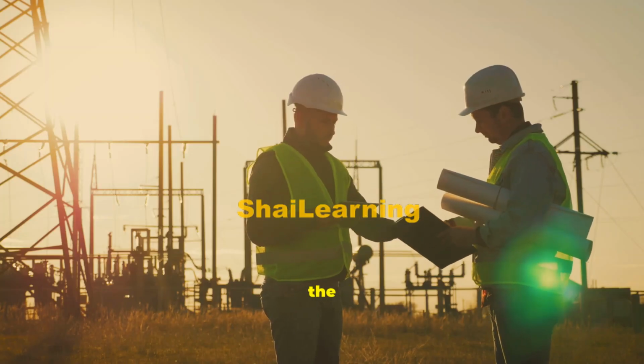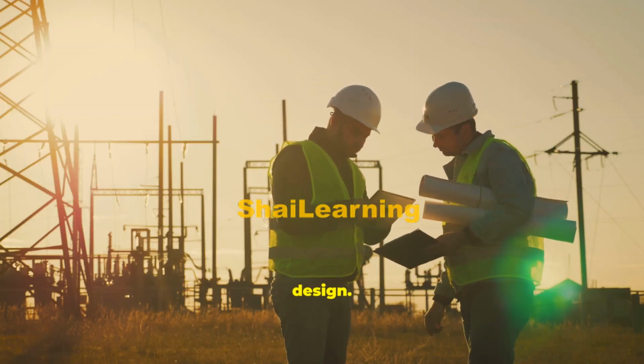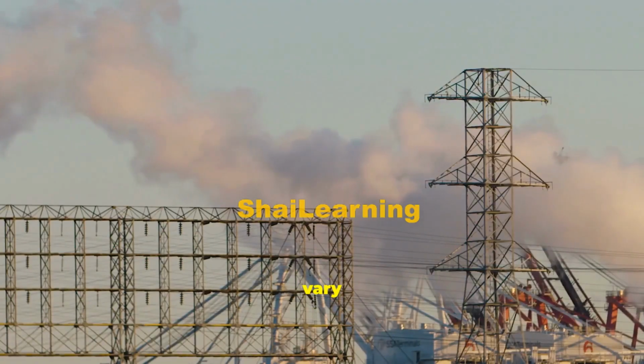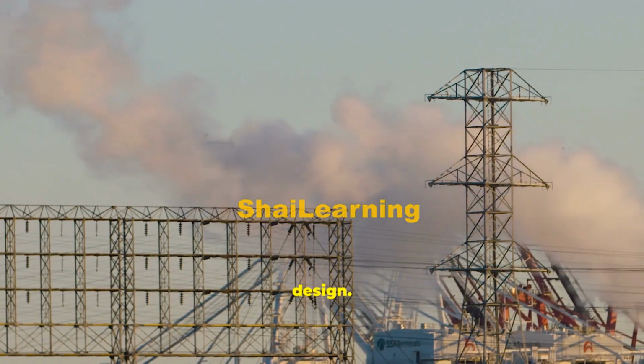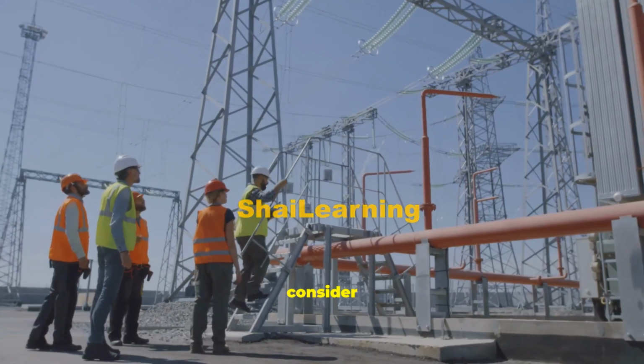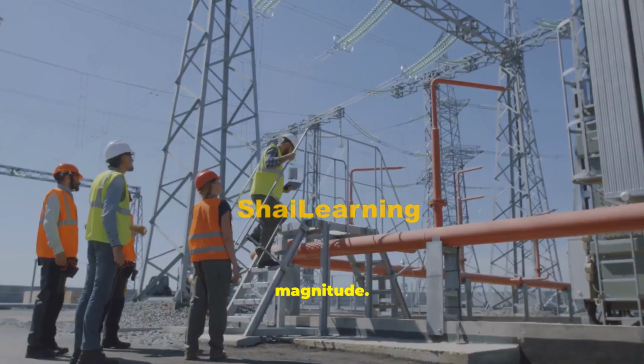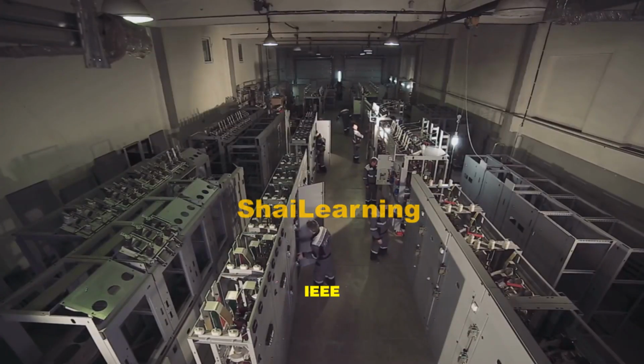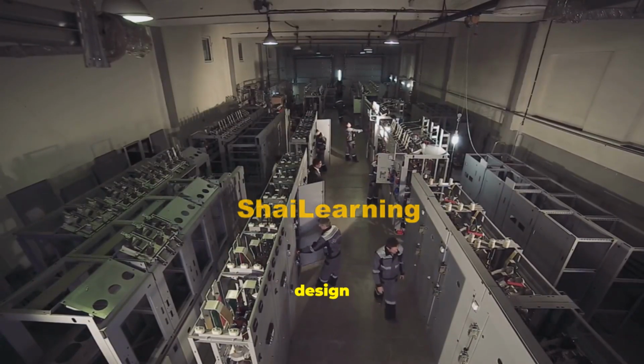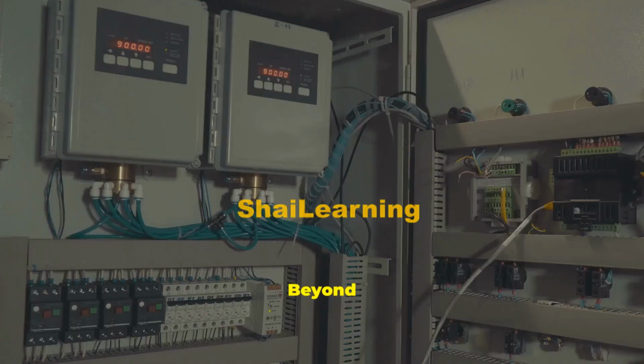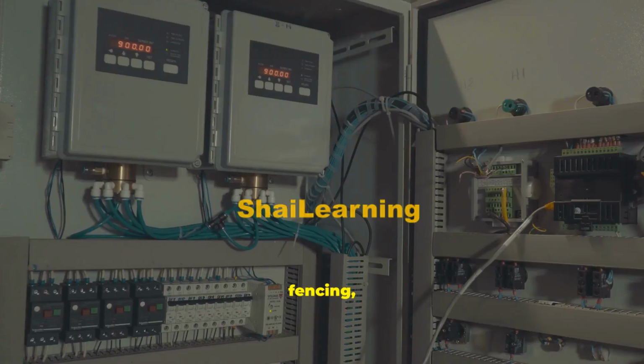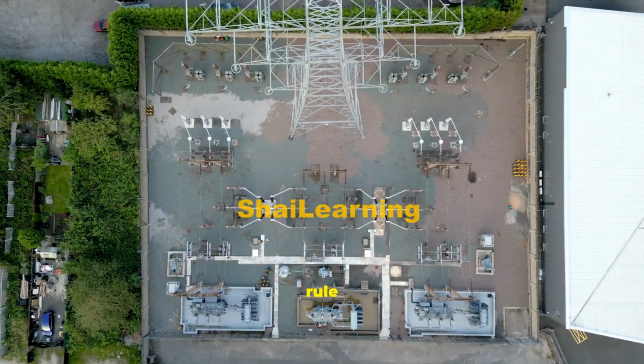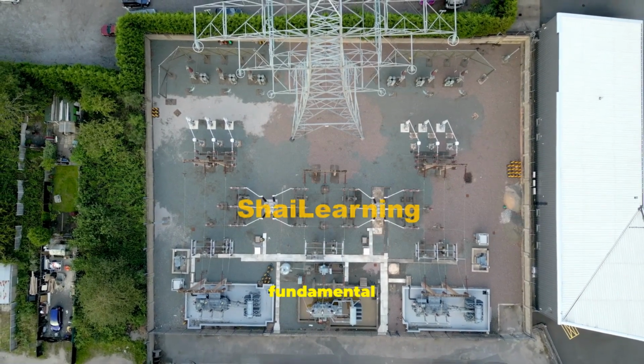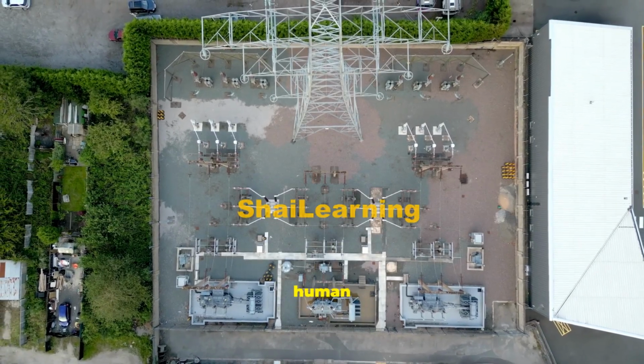Soil resistivity is the most important input to ground grid design. Different soils vary widely and impact the design. Engineers also consider maximum fault current magnitude. Standards like IEEE Standard 80 provide detailed design and testing guidance. Beyond grounding, secure fencing, clear warning signs, PPE, and rigorous lockout-tagout procedures. Every rule and every piece of equipment is there for one fundamental reason: to protect human life.